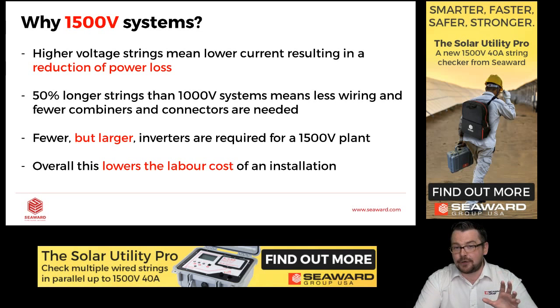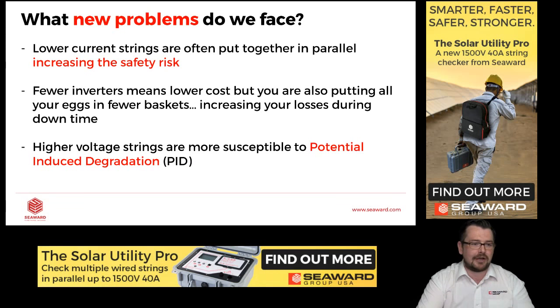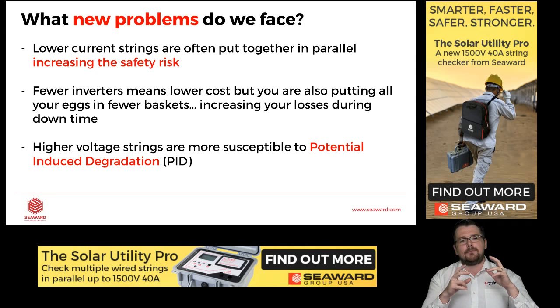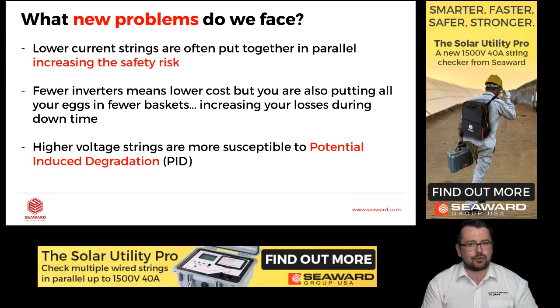So that all sounds very good, but there are some drawbacks and there are some things we should watch out for. Lower current strings are often put in parallel. Okay, so what this does is this multiplies the short circuit current. So if we have an 8 amp string and we put two of those in parallel, basic electronics tells us that that's 16 amps. And we have multiple strings going into a single fuse in the combiner box.